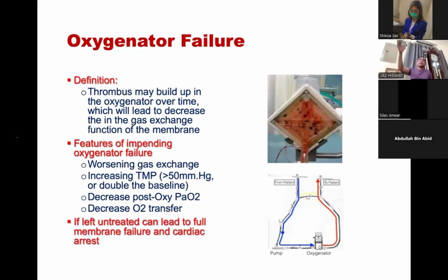So when the trend of the post-oxy is coming down, it indicates that your oxygenator is going to fail. And third, you can use a torch to do a physical examination of the fibrin in all the corners. If you find stagnation of blood or a clot, it will also indicate oxygenator problems. And number three, the last, is a decrease of oxygen transfer. The oxygen transfer formula is very important, and this is a long subject; we can talk about it separately.